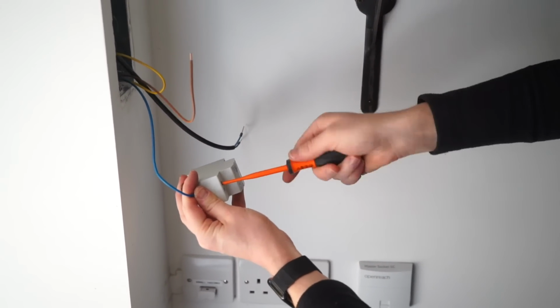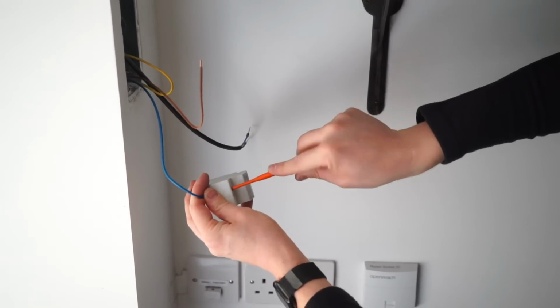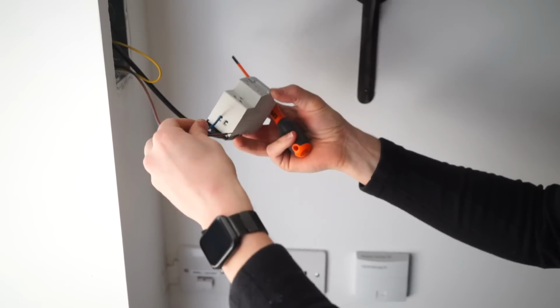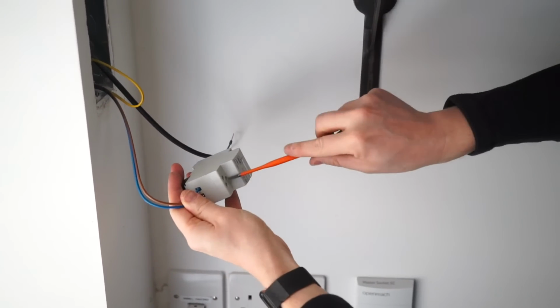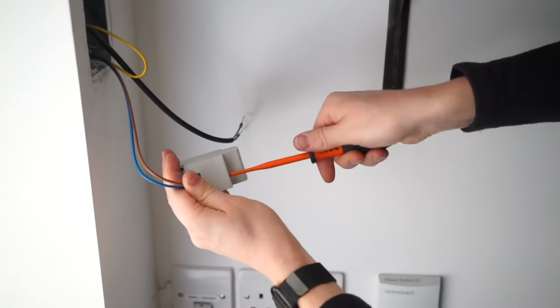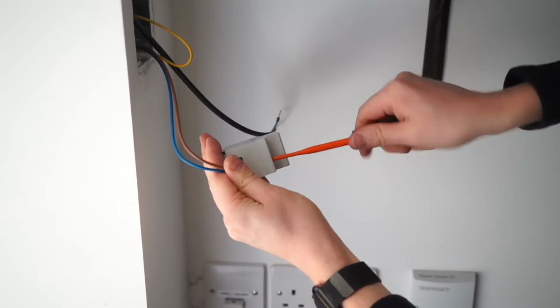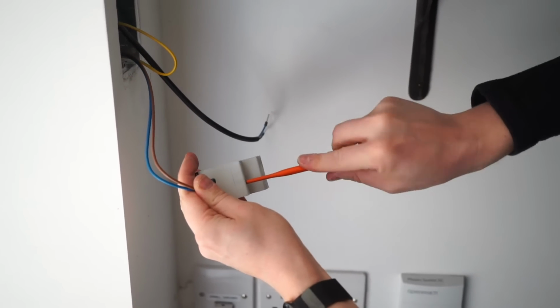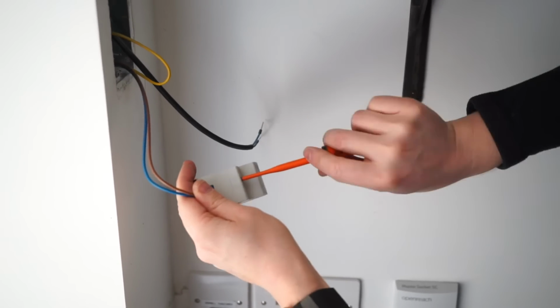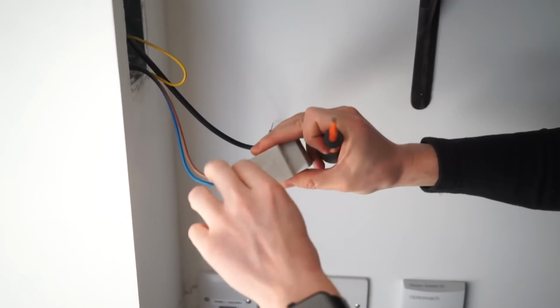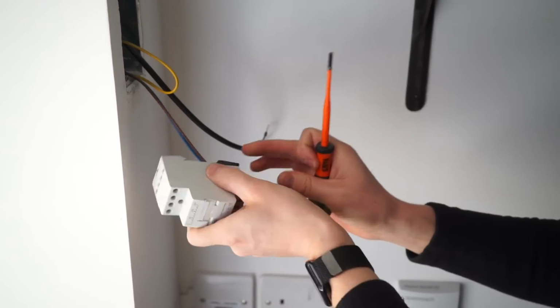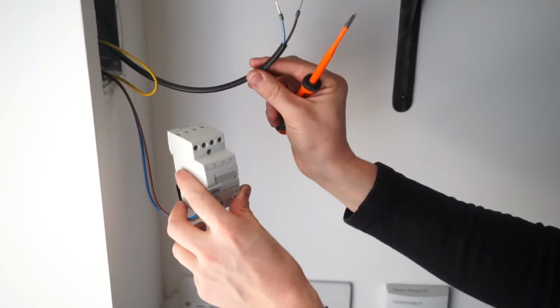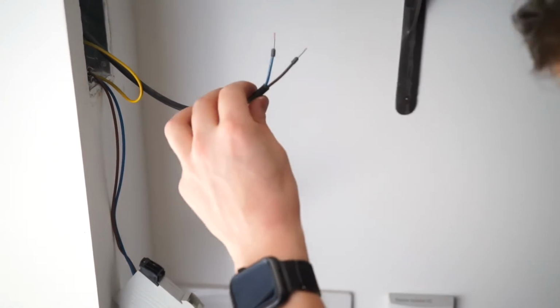Just connect that in, like so, then the live in the other side, or line as the technically correct term is. Make sure those are nice and secure in the terminal, give them a little tug, make sure they don't pull out. Then we've got to connect this low voltage cable to the outgoing side of the transformer.